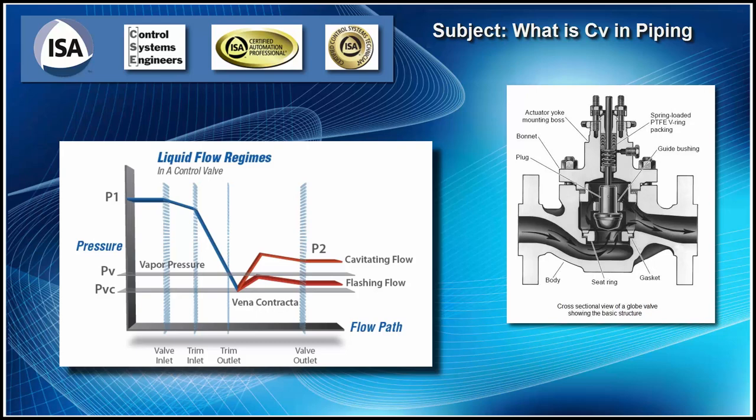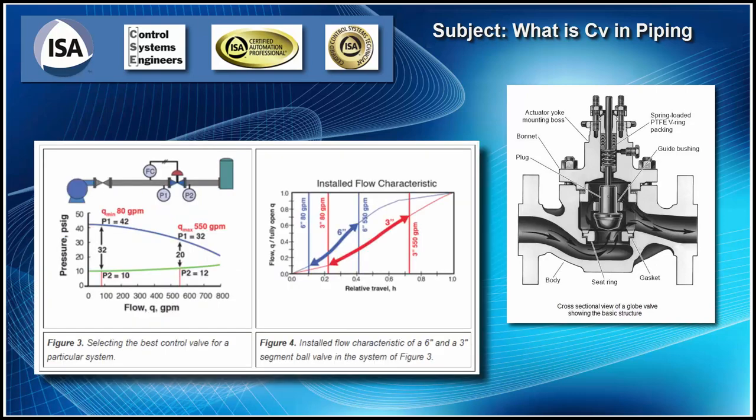We'll learn how to size valves in our instrumentation lesson on valve sizing. But I just wanted to bring up what CV was, and remember that you can't get 100% of your CV. That CV curve always flattens out. Again, when we lower our flow rate, our pressure increases, so it wants to flow faster, and we have to close the valve down more. And when we open the valve, our pressure wants to drop, so we lose CV, and we have to open the valve a little more, and we just can't get any more flow out of the valve.